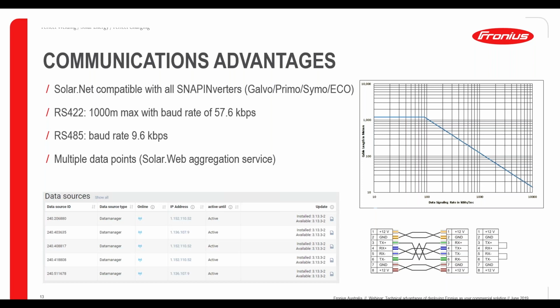Why do we mention this? With our communication protocol, as we said, we typically use 422. This tells us we can go up to around 1 kilometre in maximum string length, which is quite a bit and offers quite a few flexible options. In regards to the smart meter communication capability of 485, the baud rate is set to 9.6 kilobits a second. With the inverters, it's 57.6.